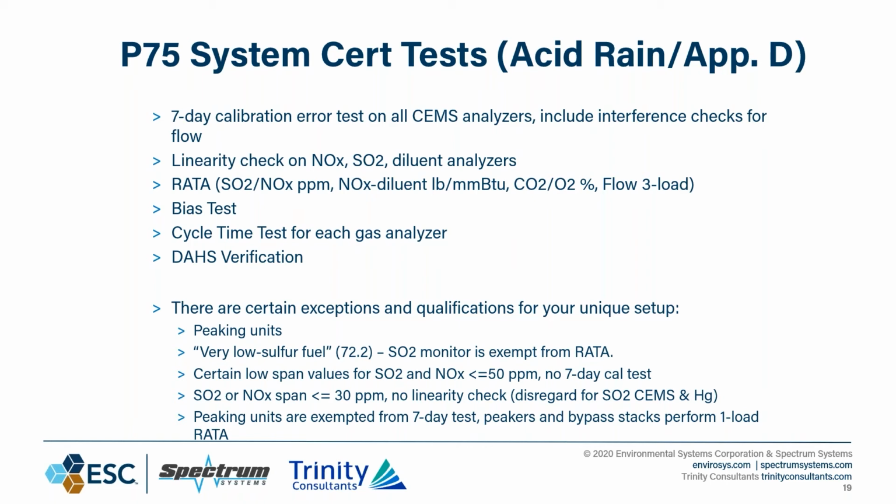Yes, I remember that you and I had to do that write-up just recently. It is unfortunate that even though they describe a Coriolis meter, they don't call it out by name under Appendix D. They'll call out a Venturi, they'll call out a couple others, but Coriolis, even though it's been around forever and a day, they just describe it. They don't call it out by name. Exactly.